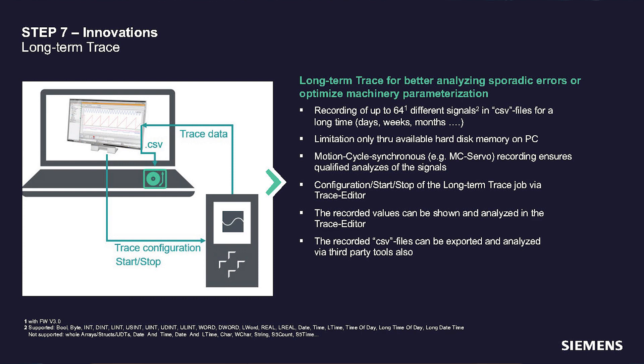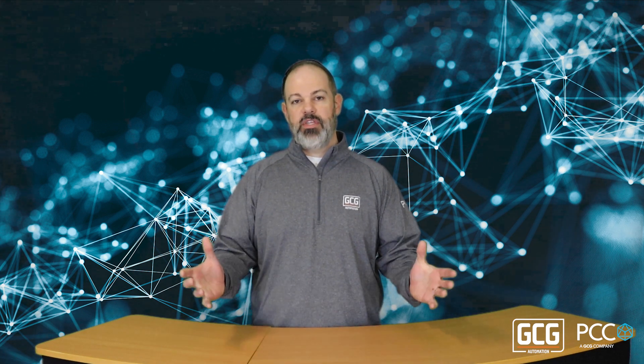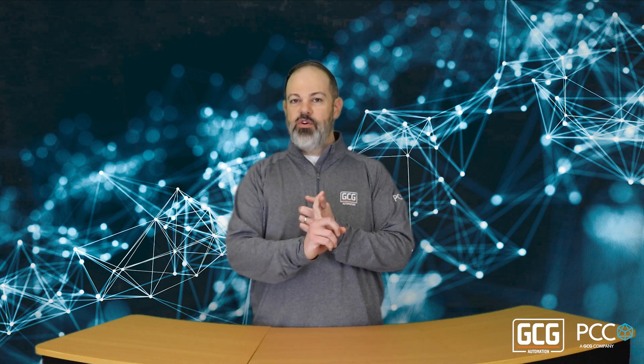What Siemens has instituted with v18 is now it's your call. You can either do the limited amount of data and trigger it based on an event in the PLC, or you can do what we call a long-term trace. That means you can keep a PC connected to the PLC, start that tracing, and leave it going as long as you'd like — as much space as you have on the hard drive where you're storing the data is how much you can record.